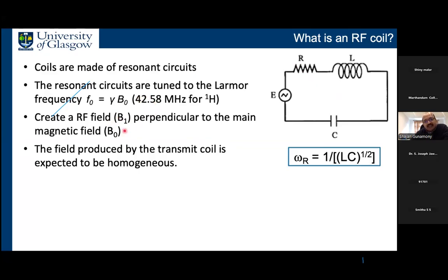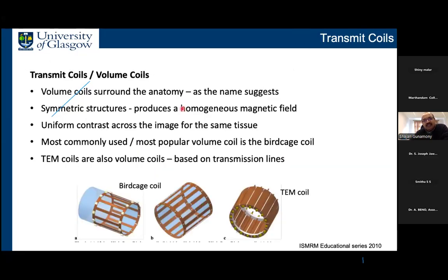So as I said earlier, the field produced by the coil will always be perpendicular to the main magnetic field. And for a transmit coil, we expect the field produced to be homogeneous. The transmit coils are also called volume coils because they surround the anatomy. As the name suggests, they are called volume coils. And as you can see in these photographs, they are symmetric structures. So we can apply a current which is uniformly distributed in this structure. Because the current is uniform, it produces a homogeneous magnetic field. And it's also important to have a homogeneous magnetic field because then you produce a uniform contrast across the image for the same tissue type.